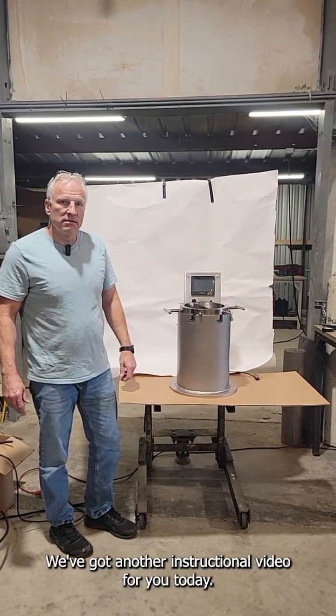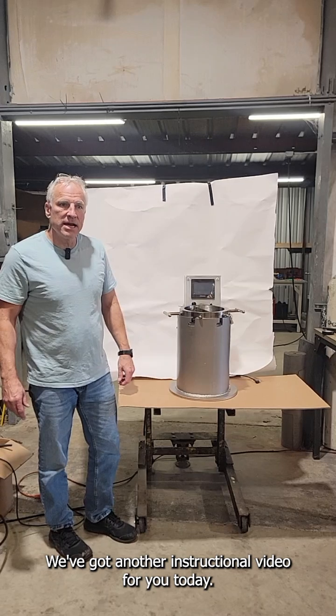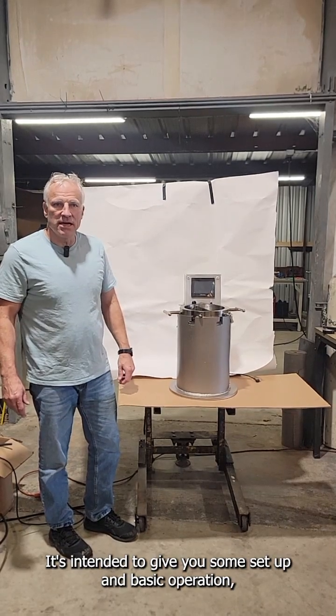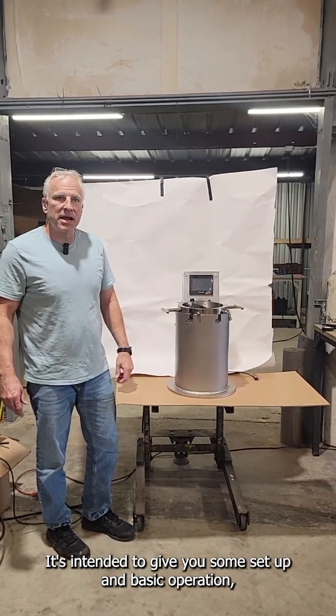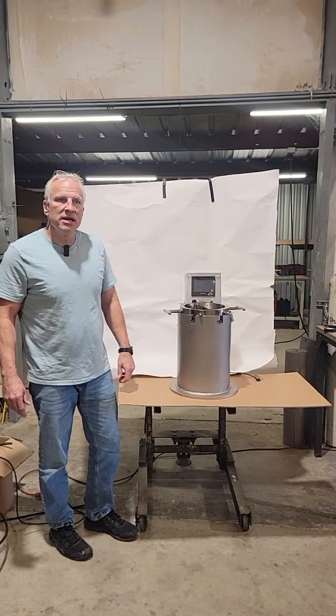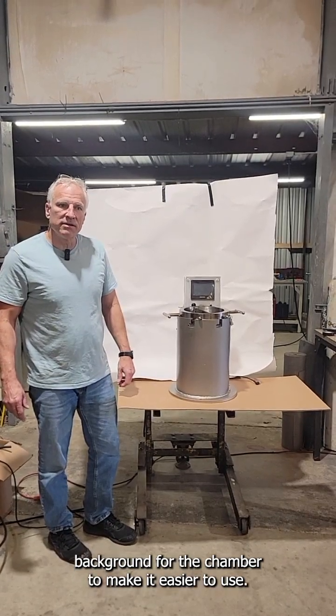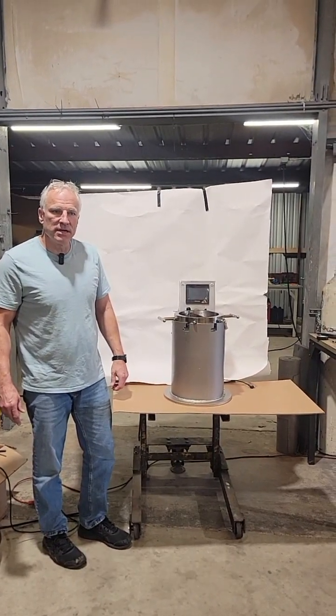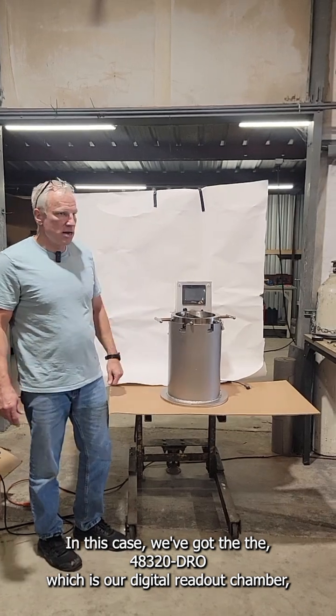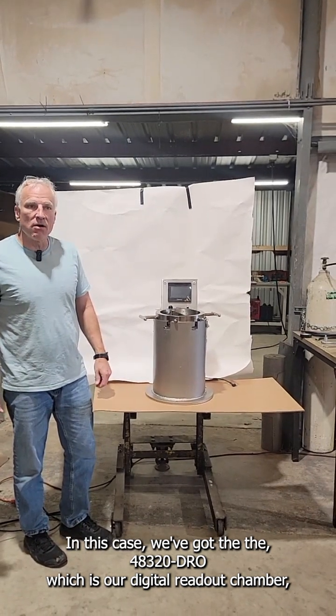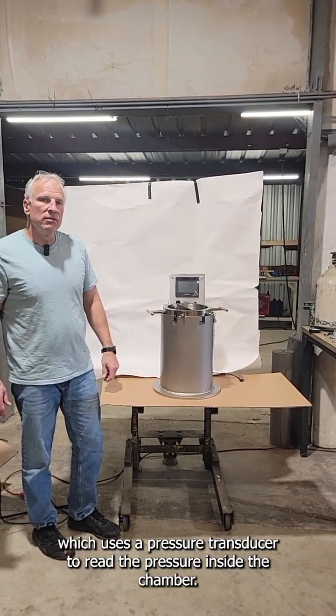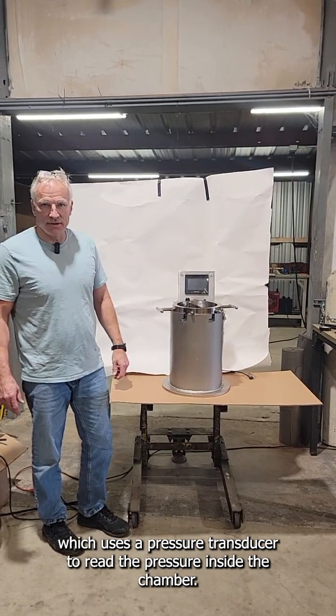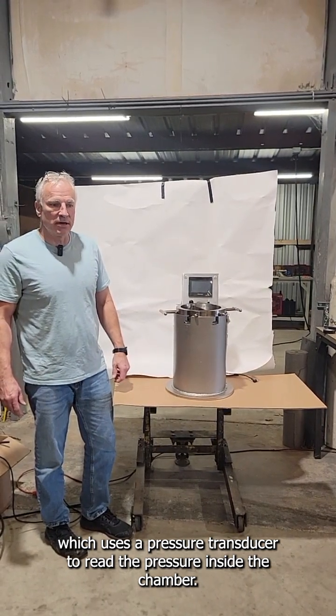We've got another instructional video for you today. It's about our test chamber. It's intended to give you some setup and basic operation background for the chamber to make it easier to use. In this case, we've got the 48320-DRO, which is our digital readout chamber, which uses a pressure transducer to read the pressure inside the chamber.